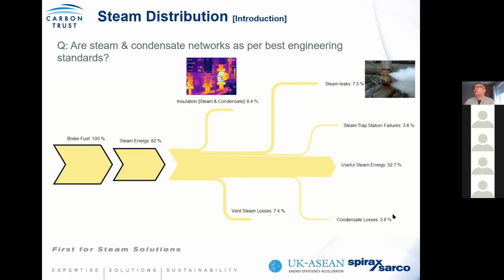If this is a regular occurrence, again, don't just fix the leak in the sense of, yes, that will address your steam leak, but you need to look at why your leaks are occurring, which is what we call root cause analysis. Look at your water quality, see is it acidic, see are you removing the oxygen, and does the water quality have an impact on the ability of the steam system to basically maintain the self-contained system without loss. Again, we're looking at traps.